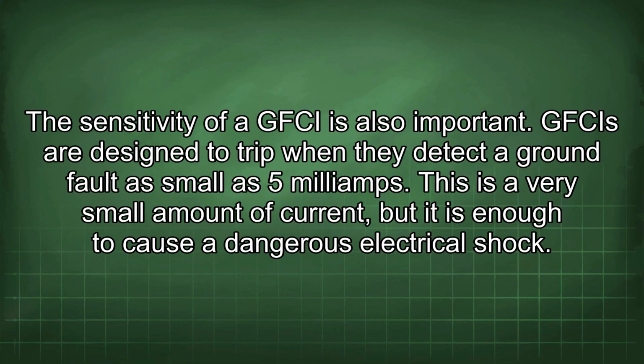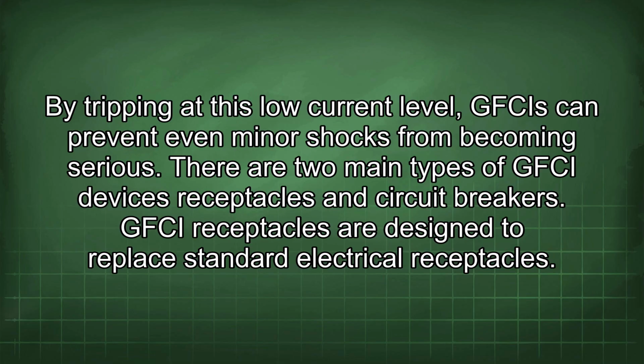The sensitivity of a GFCI is also important. GFCIs are designed to trip when they detect a ground fault as small as 5 mA. This is a very small amount of current, but it is enough to cause a dangerous electrical shock. By tripping at this low current level, GFCIs can prevent even minor shocks from becoming serious.